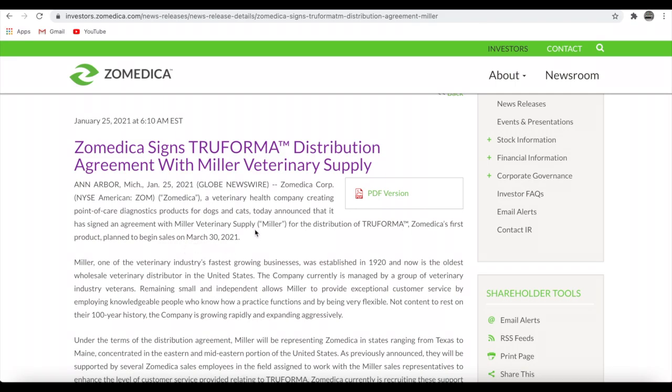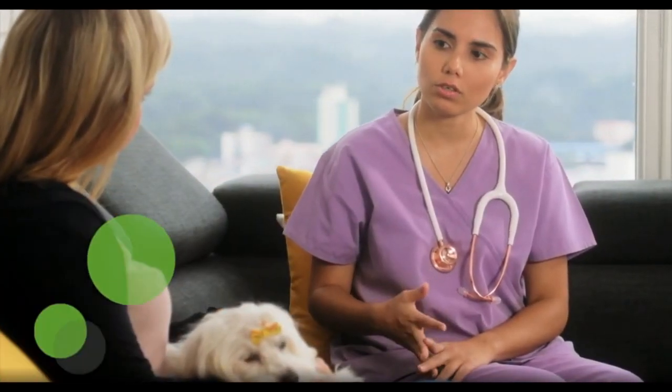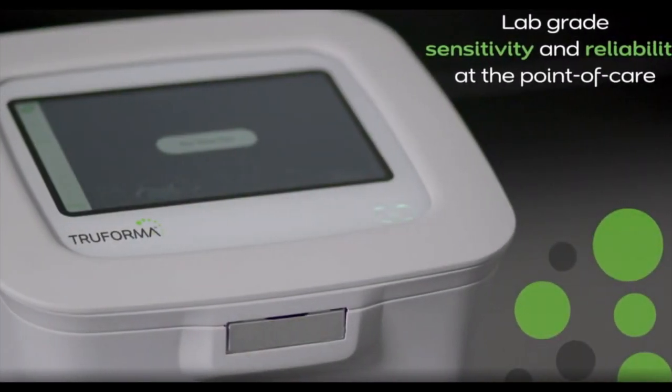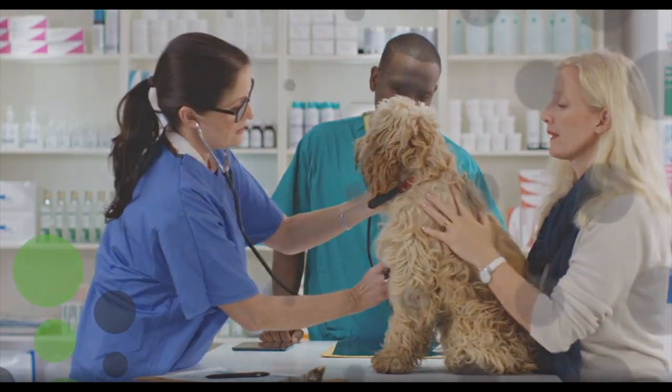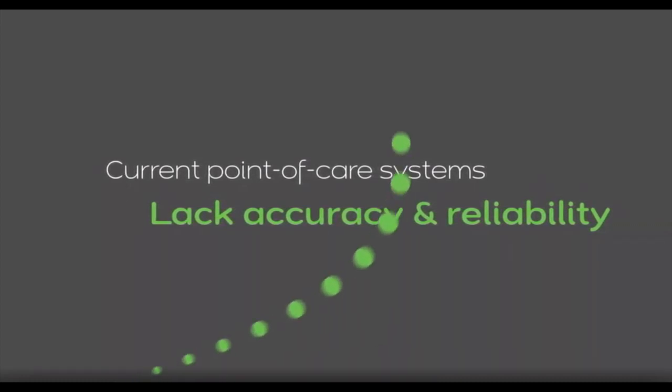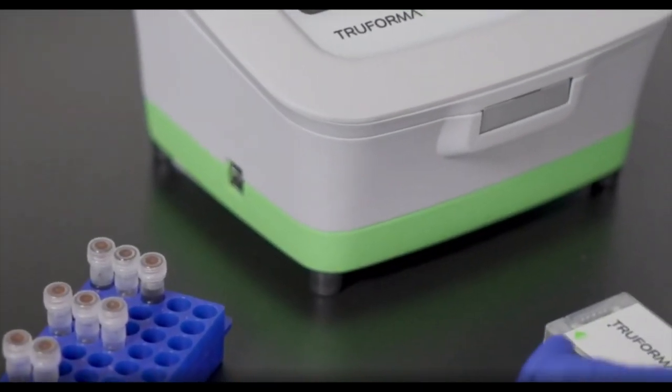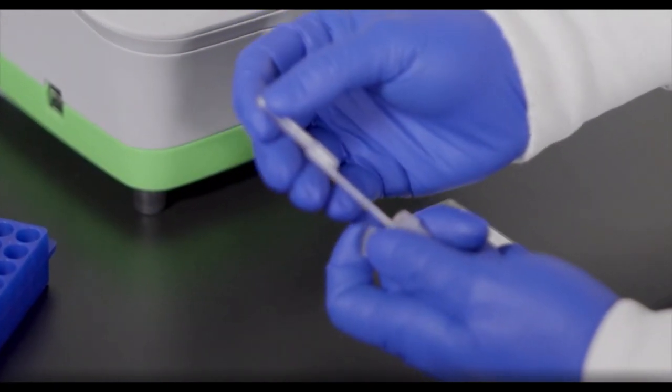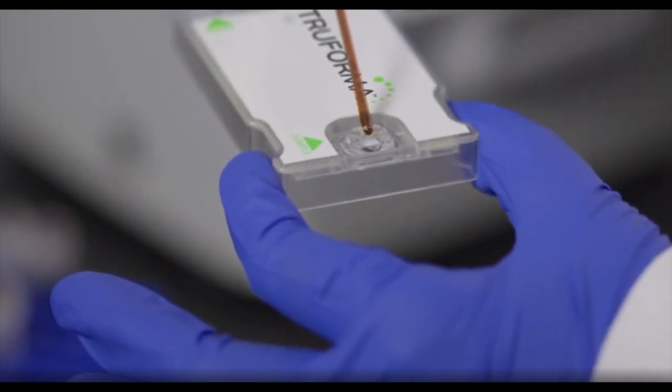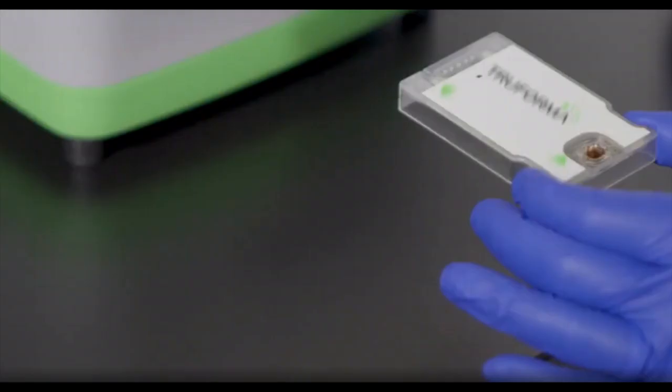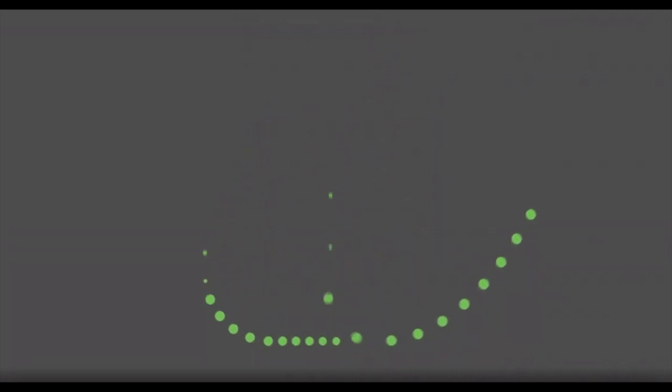This is a very crucial day. Let's take a look at the TRUFORMA itself. A breakthrough testing platform that aims to dramatically improve how we identify and manage disorders of dogs and cats. Based on high performance bulk acoustic wave detection, TRUFORMA provides accurate reference lab grade results in approximately 18 minutes on average. Currently many in-clinic platforms lack the sensitivity and speed needed for rapid diagnosis. As a result, many tests are still sent to a reference lab. The advanced biosensor platform TRUFORMA will shift this paradigm, offering fully realized reference lab performance at the point of care. Using industry standard microfluidic and electronic designing, both the instrument and the disposable cartridges are easy to use. The cartridges provide incredible flexibility, performance control, and a broad menu of complex testing possibilities. The sample passes through the cartridge via a series of microfluidic channels and ultimately over the sensor where the platform's incredible acoustic-based technology takes over.